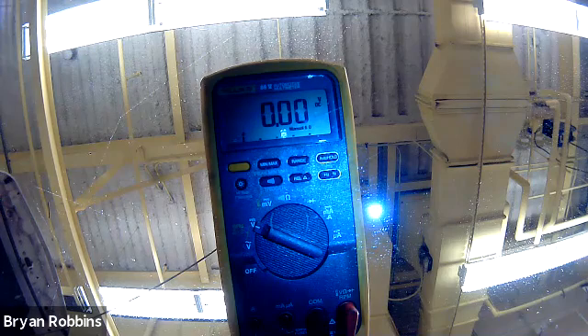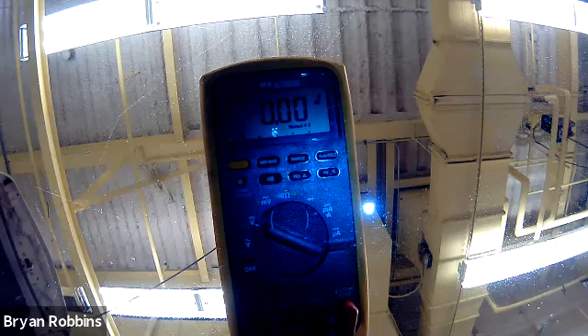I'm going to go check my connections and perform that test one more time, just to make sure we aren't dealing with a false reading from resistance caused by my test leads not being hooked up tight enough. I tightened up our connection there, wedged in the probe a little bit better. Let's see if we get a better reading, or if there's too much resistance on the ground side of this circuit.